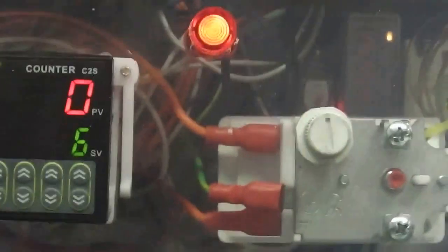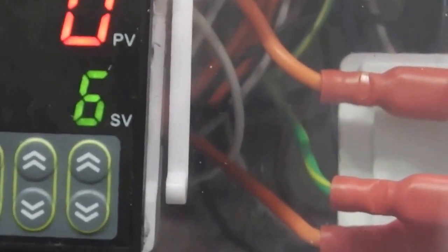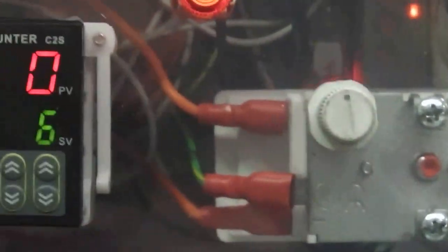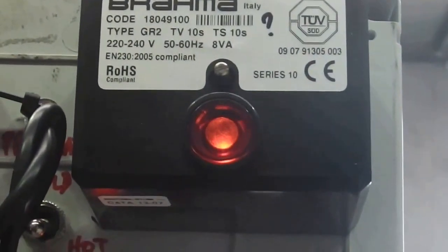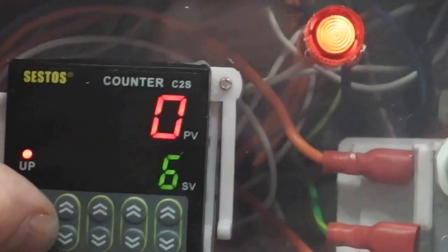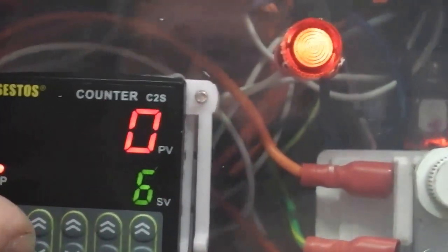It means that the burner gun will have six opportunities, set by that green number six there, the set value, six opportunities in this case to do restarts. And pretty much after that, it'll just sit there forever until the client comes up and sees, hey, we've got a flame failure here, the present value is down to zero, and what the customer should do is investigate the problem.